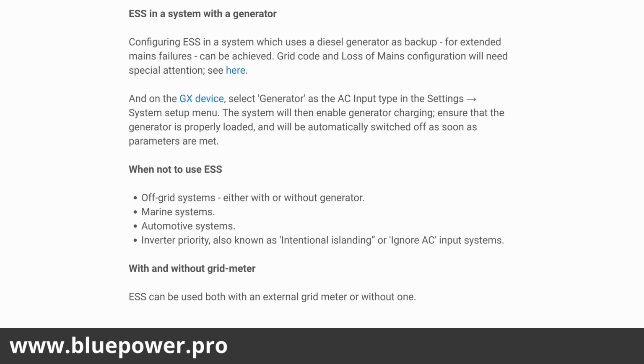So in ESS systems with a generator, configuring ESS in a system which uses a diesel generator for backup or extended mains failures can be achieved. So grid codes and loss of mains configuration will need special attention here. That's where we have to take note of which input we connect our generator to if we've got it connected to a system, and make sure that we've got the LOM detection switched off.